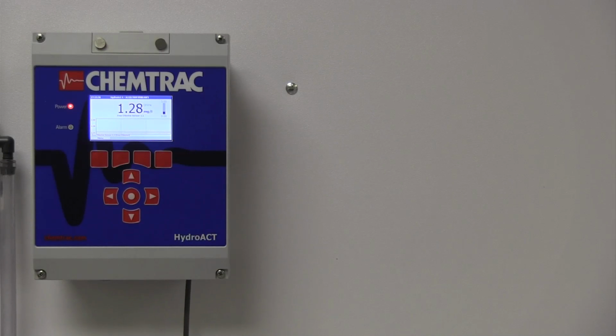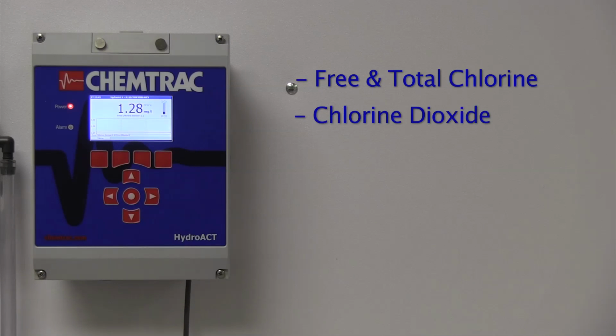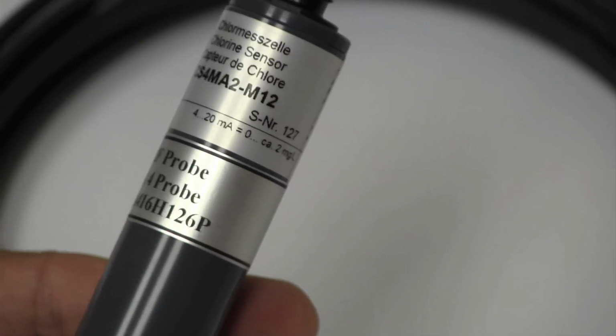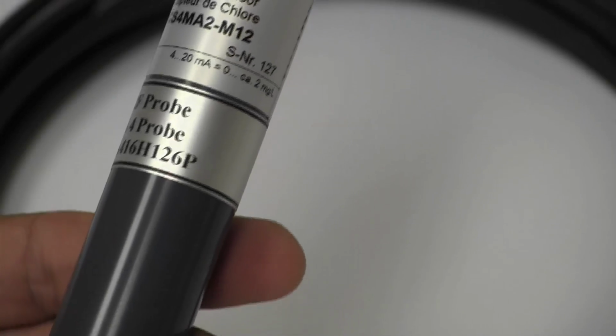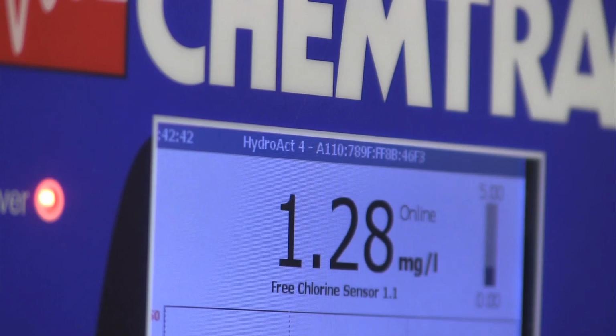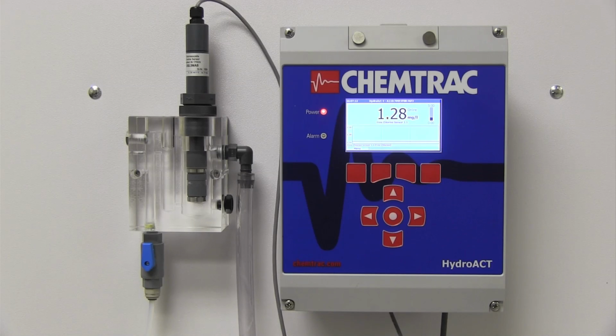The Hydroact Analyzer is capable of monitoring a variety of parameters, including free and total chlorine, chlorine dioxide, ozone, ORP, and pH. The sensors are simple to install and operate, have no moving parts, and do not require a monthly replacement of reagents. We will demonstrate the easy setup and calibration of Chemtrac's free chlorine monitor, which consists of a Hydroact Analyzer, a free chlorine sensor, and a sample flow cell.